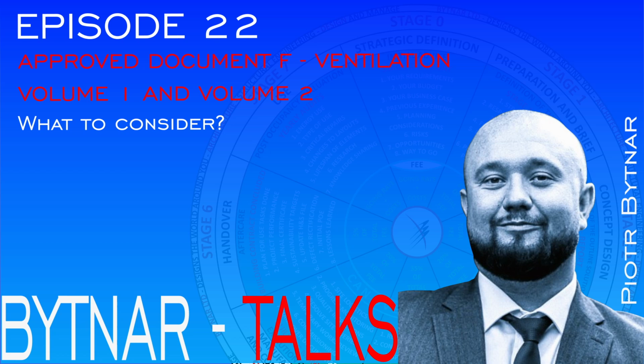Ventilation of inner rooms can be done through another room, through a permanent opening between the rooms of at least 1/20th of the combined area of the rooms, provided that the equivalent purge ventilation is possible in the access room, or the room is serviced by 10,000 millimeters squared of equivalent background ventilation.